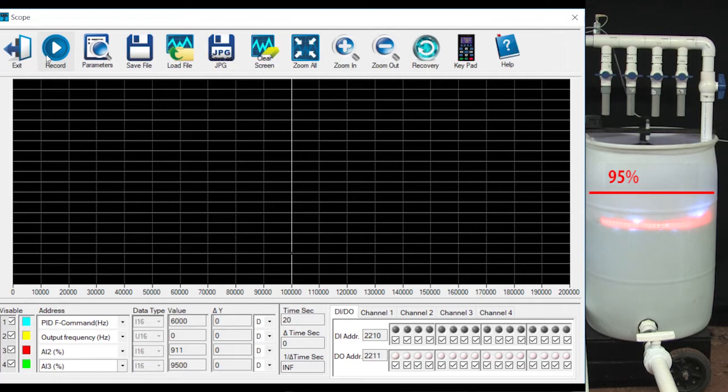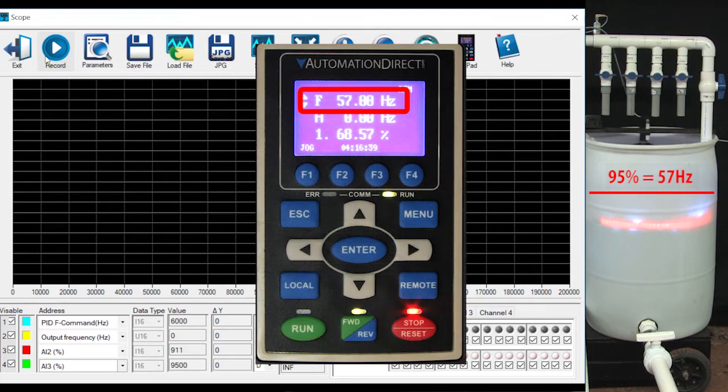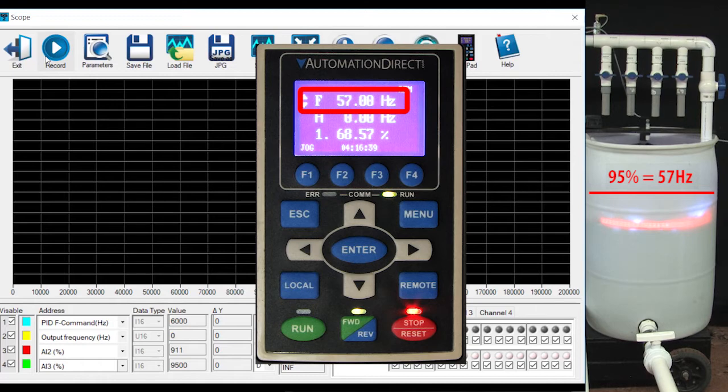Suppose we want our set point to be when a tank is 95% full. Well, 95% of our max drive speed of 60 Hz is 57 Hz, so we enter that here. Remember, because we are using PID, this isn't the drive frequency anymore – it's the set point.